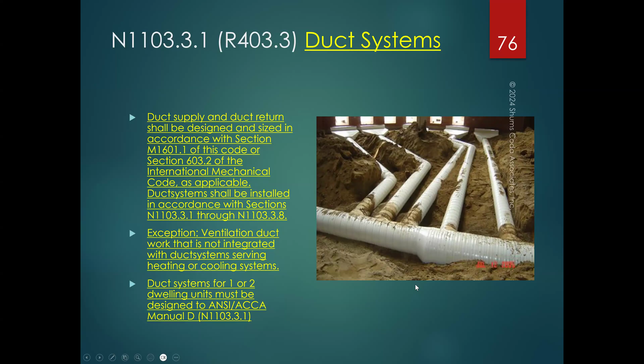All right, ducts in conditioned space. We have some updated conditions. Ductwork contained in the wall or floor assemblies separating unconditioned from conditioned space has to comply with the following. We've got a totally new updated section. As part of the building assembly, installed ductwork between the ductwork and the unconditioned space should be installed in accordance with 1103.3.3, and we can't have less than an R10, or not less than 50% of the required insulation R-value in Table 1102.1.3, whichever is greater. And then also segments of ductwork contained within building assemblies not considered completely inside conditioned space.